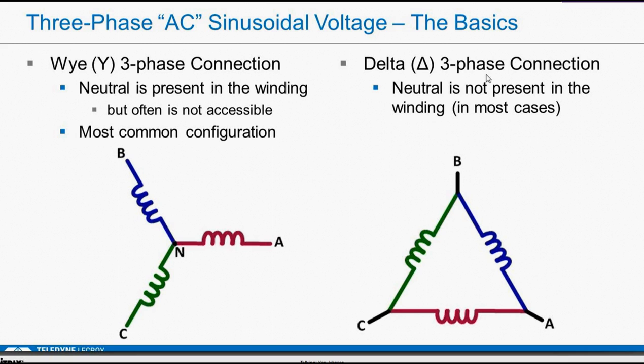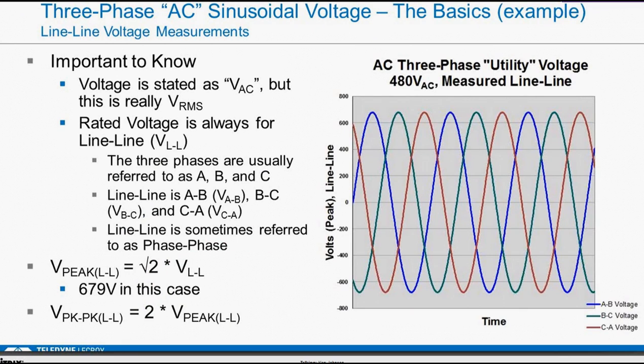You can also have a delta connection, where there is not a neutral present in most cases, and you have to measure line-to-line. Note that here, it's pretty easy. If I put a current probe or a current measurement device here, I'm measuring the current directly through the coil. Here, I'm not measuring the current through one coil if I put a current measurement device here. The current goes here, and it splits between two coils. So, a subtle difference of note for people making those kinds of measurements.